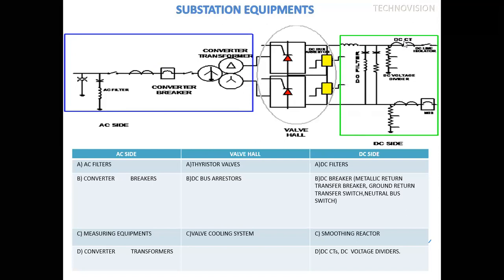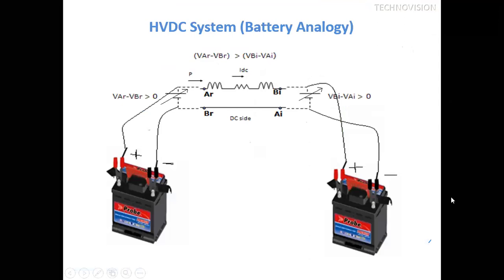And for measurement of DC current, we have the DC-CT. This works on the flux cancellation principle, and this is the resistive divider arrangement. So their working is something different. And sometimes in the neutral part there are breakers that are actually not DC breakers. Conventional breakers, SF6 types of breakers, are used to isolate the system during de-energization. Otherwise you will never find any breaker on the DC side. Only the neutral part has breakers, and the AC side also has breakers.